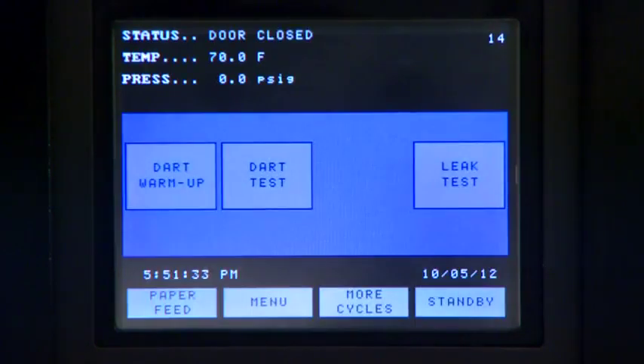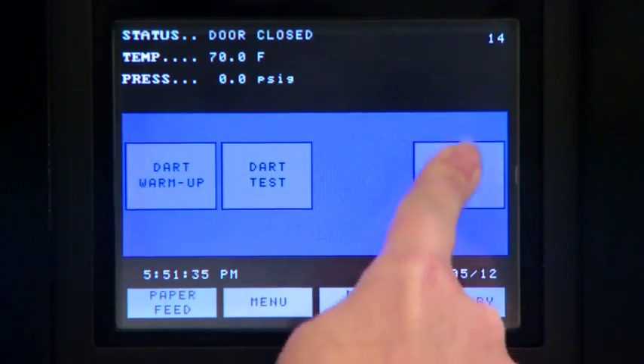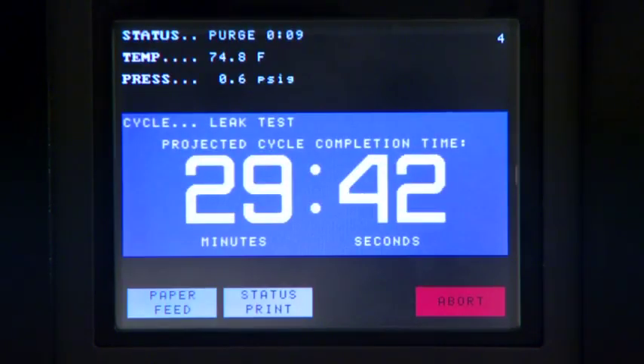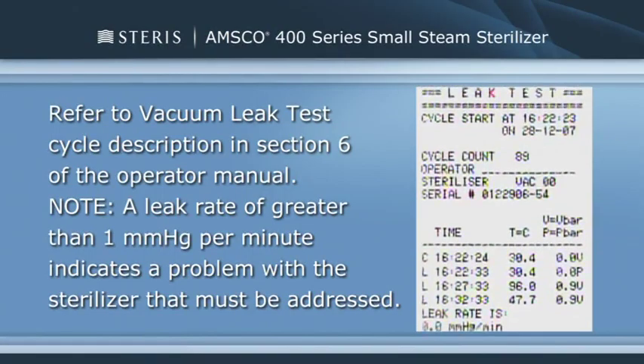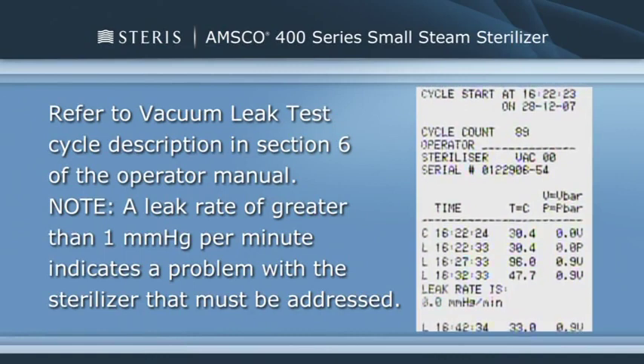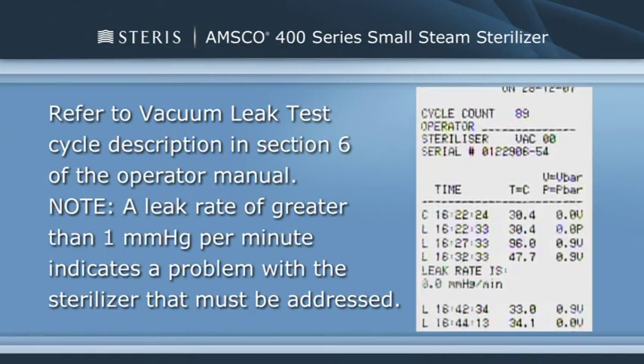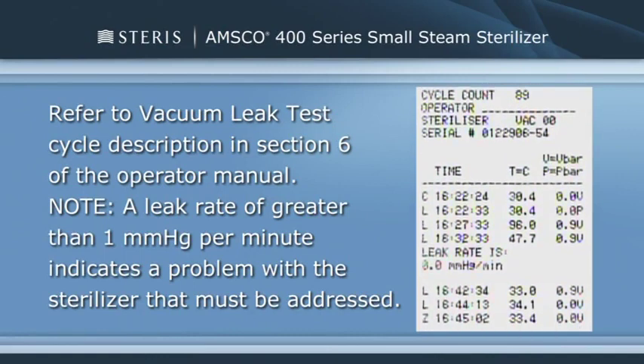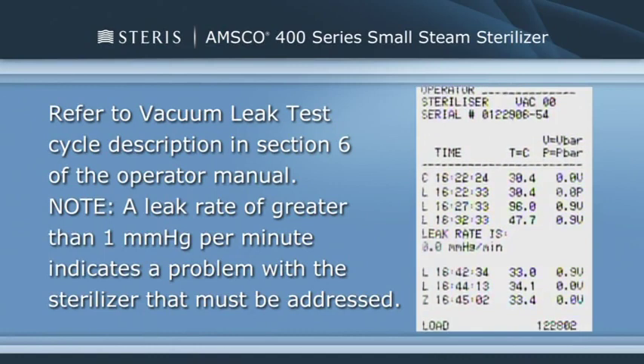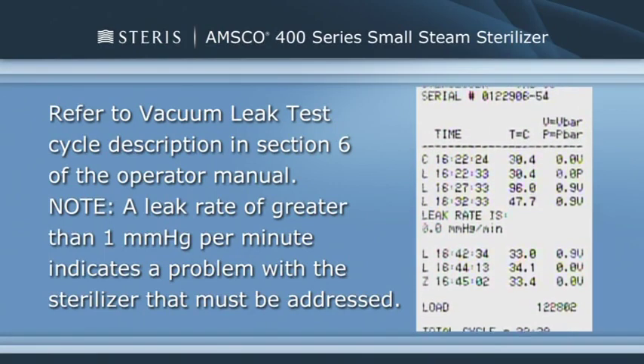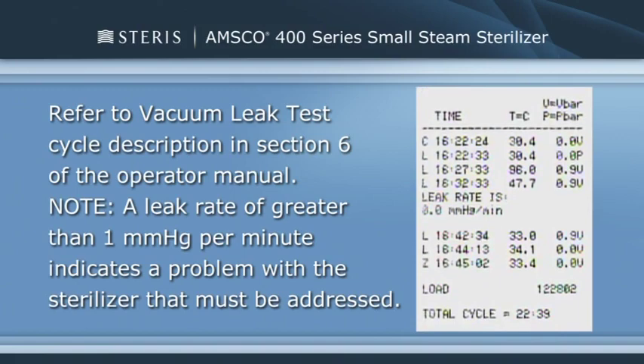The vacuum leak test cycle, which should be run daily or weekly, measures the integrity of the sealed pressure vessel and associated piping to assure air is not being admitted to the sterilizer during the vacuum drawdowns. After running a leak test cycle, a value or leak rate will be printed on the printer tape. This value will help define a trend over a period of time if the integrity of the system begins to deteriorate or allow air to enter the system.